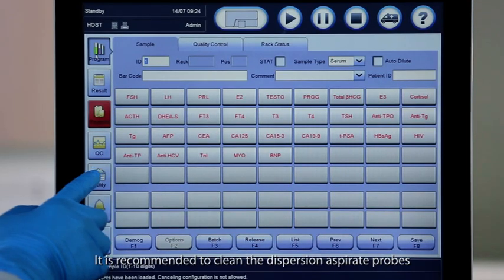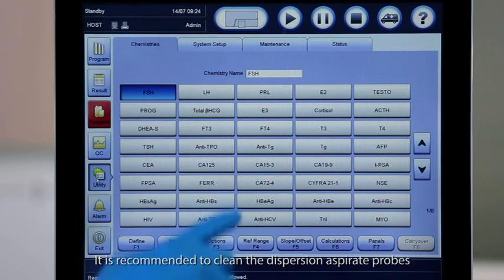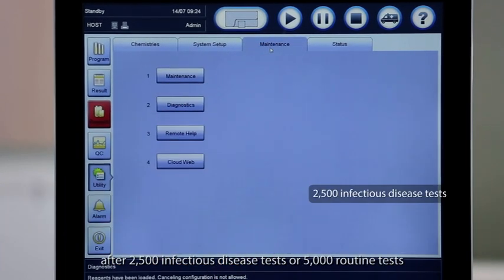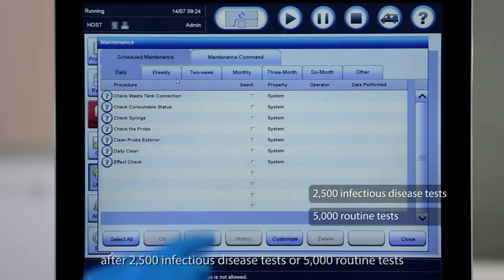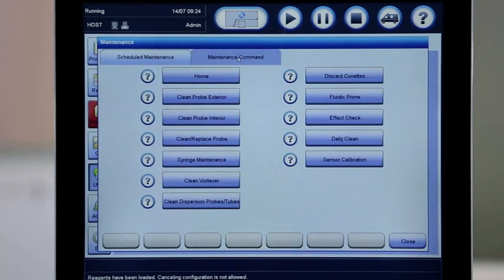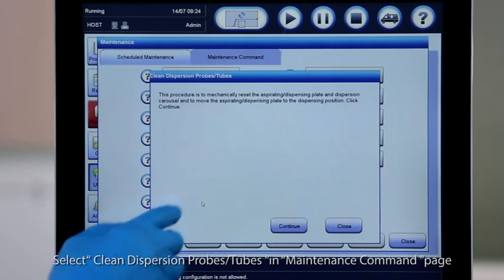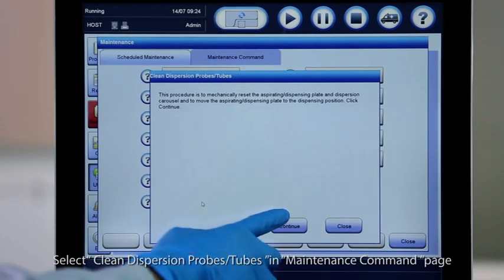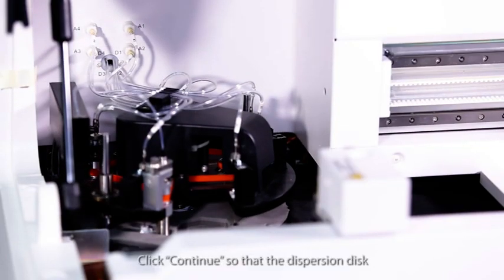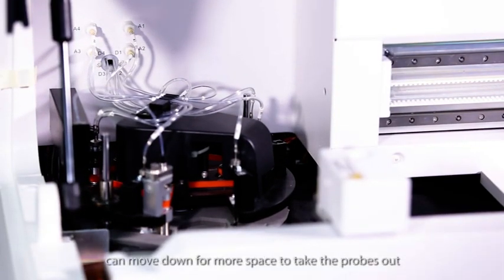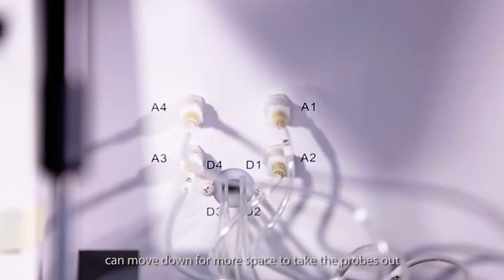It is recommended to clean the dispersion aspirate probes after 2500 infectious disease tests or 5000 routine tests. Select Clean Dispersion Probes in Maintenance command page. Click Continue so that the dispersion disk can move down for more space to take the probes out.